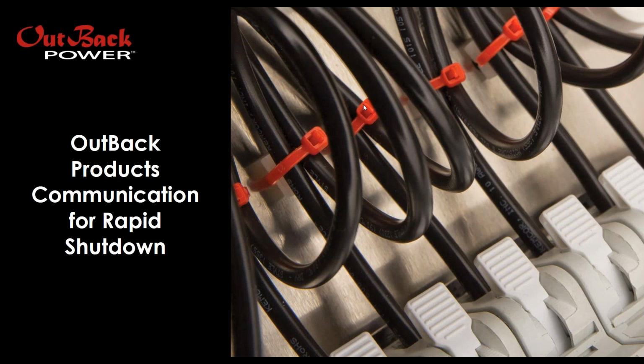Okay, so now we're going to talk about the communications portion of this. So we will review what is needed to communicate with OutBack products in order for the FM100 or SkyBox to perform a rapid shutdown and to ensure that there's no back voltage to the PV conductors. So we do have an application note that has more details on the NEC 2017 solutions. It's a guide for that, and it's available at outbackpower.com, and I will show you later live where you can find that.